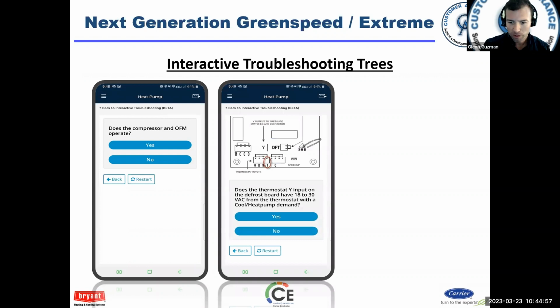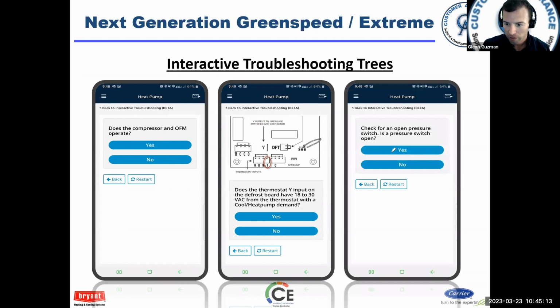Here it's showing you a picture of the schematic: do you have 24 volts on Y, between 18 and 30 on Y? Yes or no—so you can see how this is walking you along. If you got it there, great. If not, hey, maybe there's an open pressure switch, and you can check for that. That's a pretty generic and easy issue, and you probably don't need the interactive troubleshooting for that, but the ability's there, and it gets more in depth depending on what unit you're working on and the problems you have.